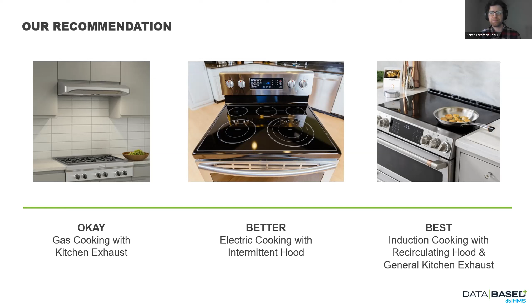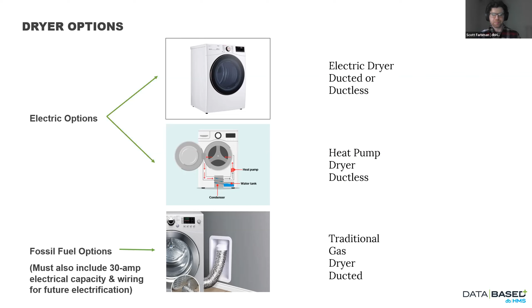Dryer options are kind of the same thing. We have two electric options: a normal electric dryer that could be ducted or ductless, or heat pump dryers, which are definitely ductless and more energy efficient. Or we have our traditional fossil fuel gas-burning dryer, which needs a duct to exhaust that combustion air. Just like the range, if you install a gas-fired dryer, you also have to provide the electrical capacity and infrastructure to change over to an electric dryer in the future, which is a 30 amp dedicated circuit and breaker in the wiring and conduit as well.